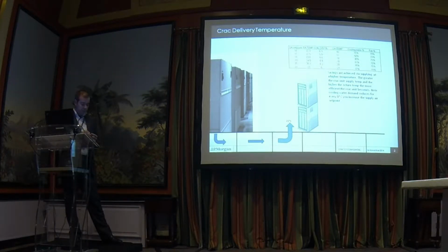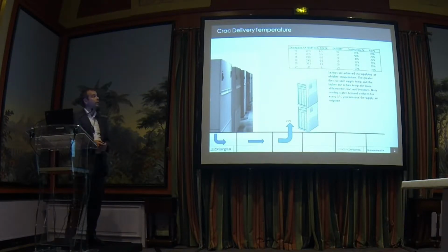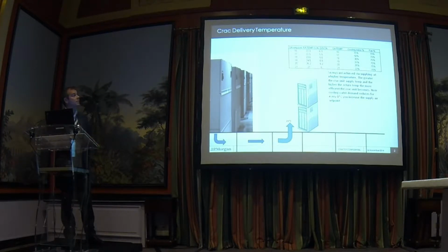So up here, some tests we've done on one of our data centers where we converted the machines to supply air control. Up there at 16 degrees, return air at 22, a 6.3 delta, that's between the air in and air out of the CRAC unit. Supply air temperature at 16, cooling water valve 75%, fans at 70%. So you go up a degree, let it run for a few hours, it'll stabilise out. Deltas are still the same, but you see they're at 50% cooling valve. So you've had a quite substantial cutback there, just for 1 degree of supply air temperature.